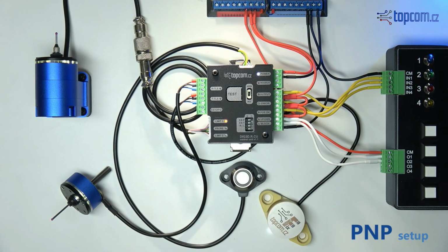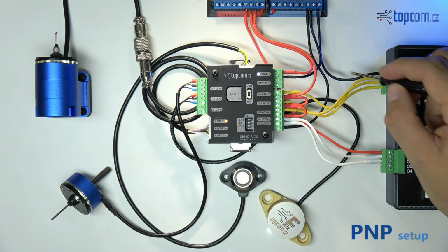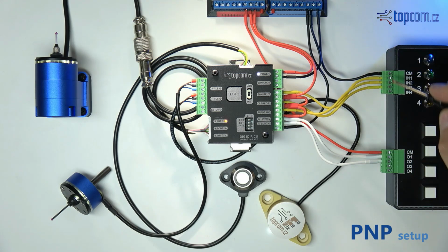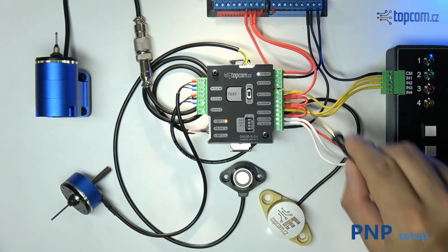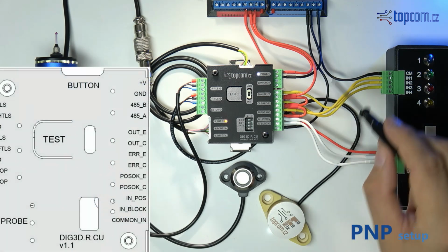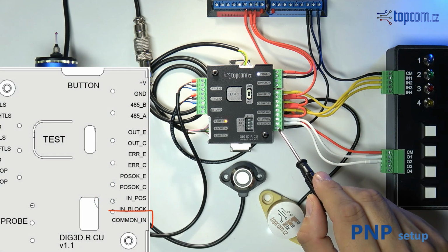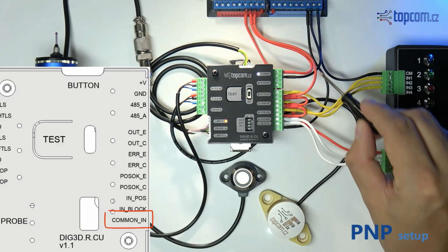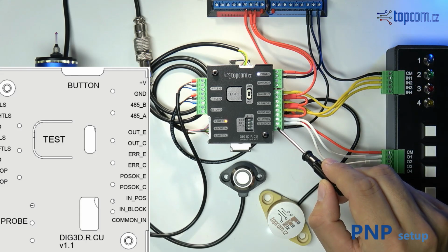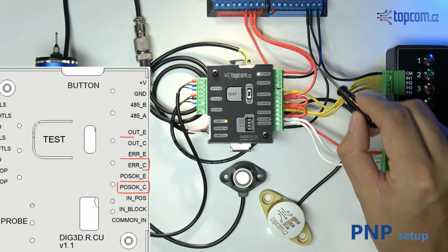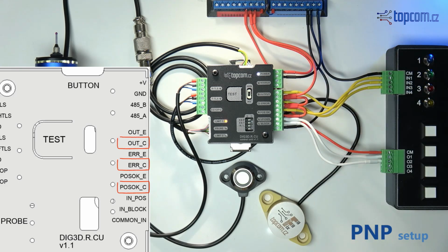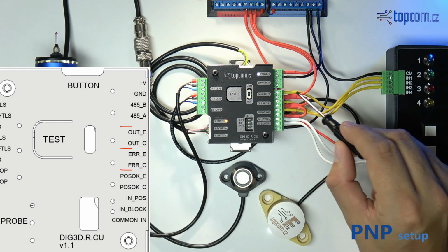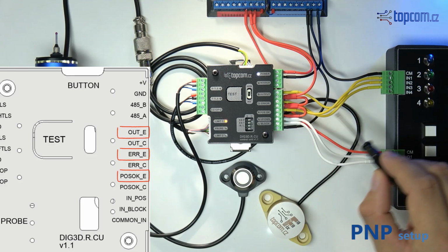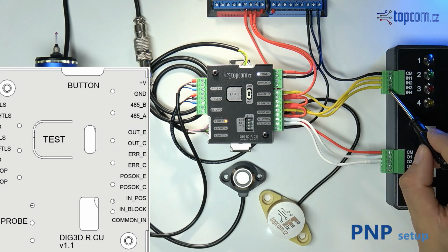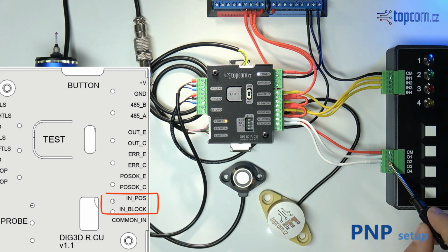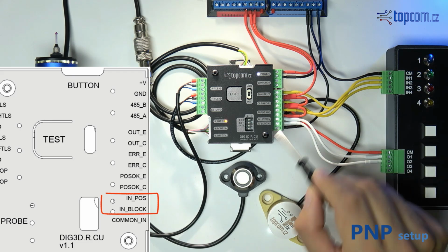In a PNP configuration, the common line for the motion control inputs is connected to ground, while the common line for the outputs is connected to the positive voltage. On the control unit side, the common input line must be connected to ground, and the output terminals labeled C must be connected together to the positive pole of the power supply. The output terminals labeled E are then connected to the PNP inputs of the motion control board. And finally, the input terminals of the control unit are connected to the outputs of the motion control board.